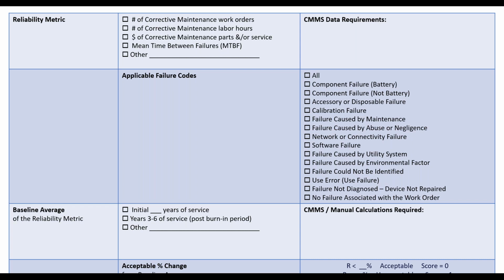But I also think that the environmental factors and use conditions, along with use and negligence, we can attribute to training in a clinical setting, working with our clinicians, working with nurses on the devices. And I don't consider a power cord to be a service ticket issue when it's a corrected issue on the clinical side. So there are some areas there that would be eliminated and not necessarily implemented into this method.